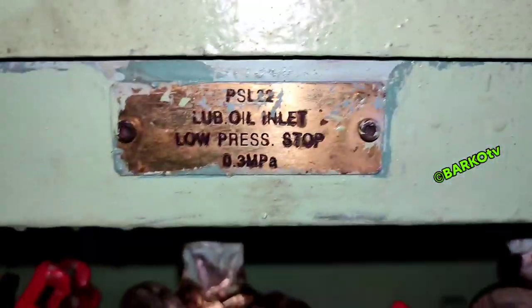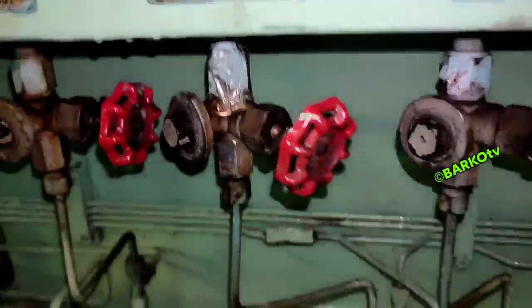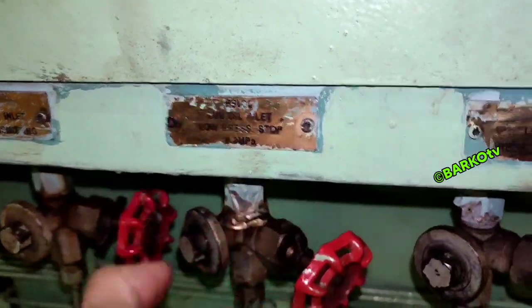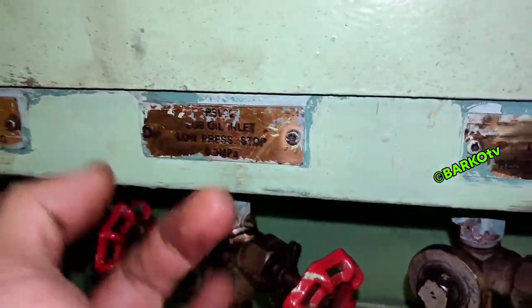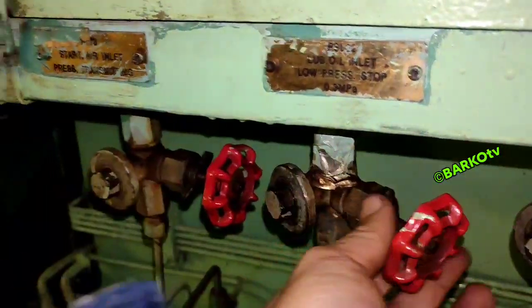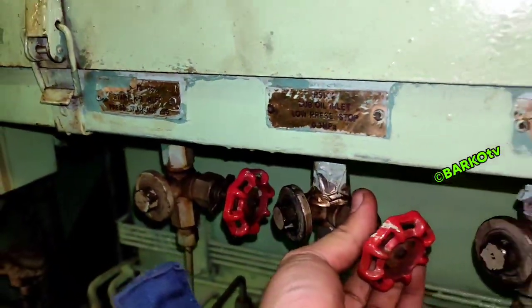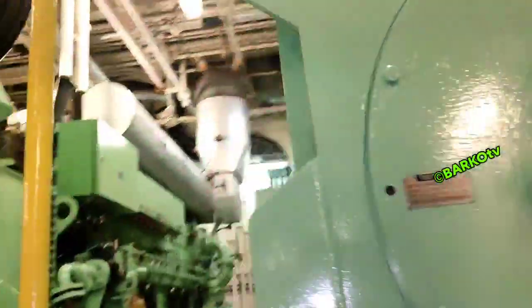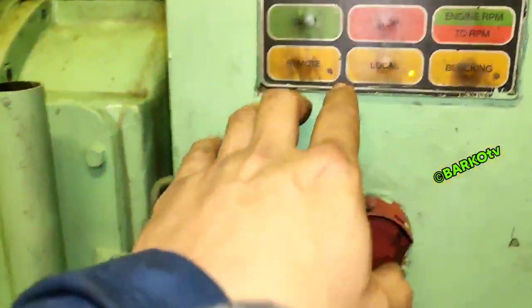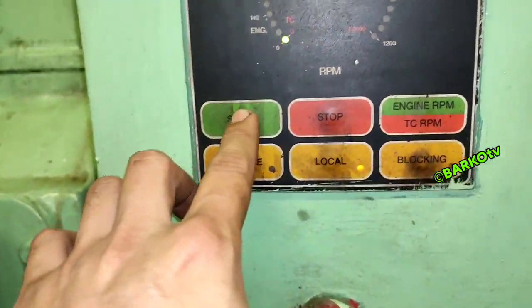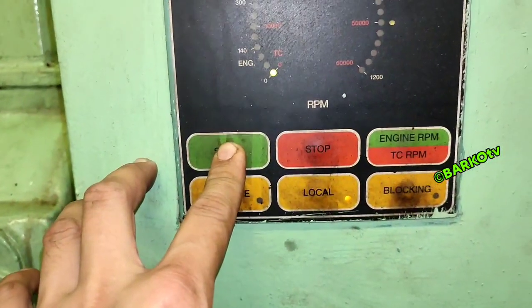Okay, put back the three-way valve to open, and then close the vent and also the securing lock nut, and let's start again. And also, if you want to actually simulate this pressure switch, use a pressure calibrator or pressure simulator. But for now, we are actually simulating this low oil pressure shutdown.